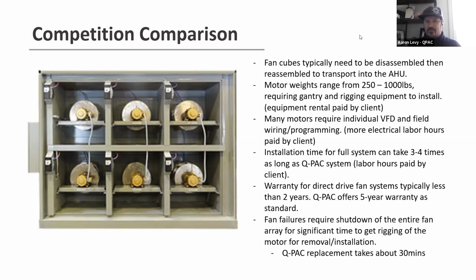We've designed the system so that if a fan were to fail or a component fails, there are backups. That doesn't make the whole world stop. It doesn't make everything as critical. You can take your time. You're not panicking. You're like, okay, I can just order a fan. It'll be here in a couple of days, and then we'll replace it. In most cases, a customer won't even know a fan's down without the alarm screaming at them. And then most of the time, they can set a shutdown over lunch hour or schedule a breakdown at the end of the day to make those changes and be ready to go the next day.